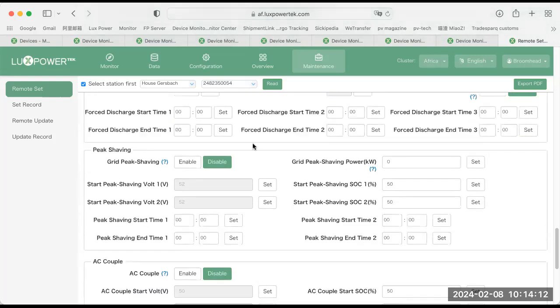All right, then we have peak shaving. Do you think anybody's using this particular function in South Africa? Is this function available for us? Yes, I know in the US. Okay, so the peak function, unless you didn't know, did you know that you can limit the amount of power that your machine imports from the grid? So in other words, when PV is on and your loads are running, you can limit.